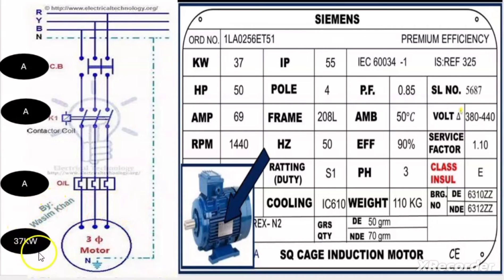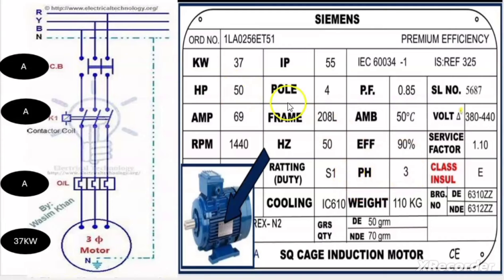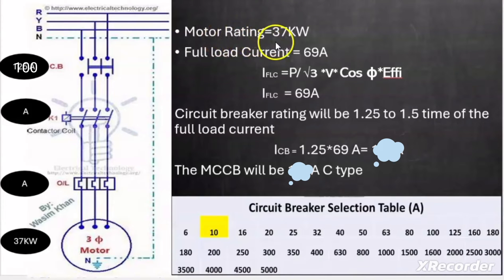I took an example where the motor rating is 37 kilowatt. Here is the nameplate of this motor: the rating is 37 kW or 50 HP, the full load current is 69 ampere, the power factor is 0.85, the efficiency is 90%, and it is a 3-phase motor. These details are important to understand the calculations. We need to calculate the ratings for the circuit breaker, contactor, and overload relay.